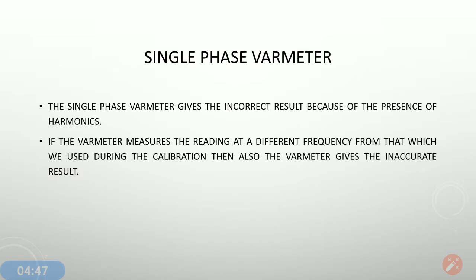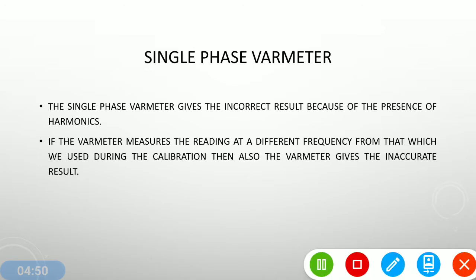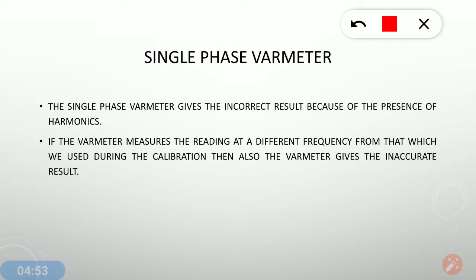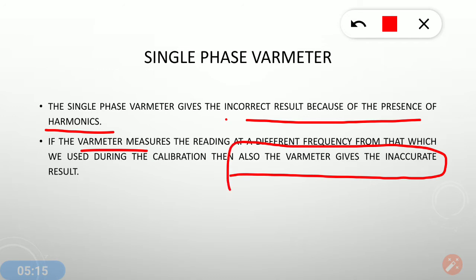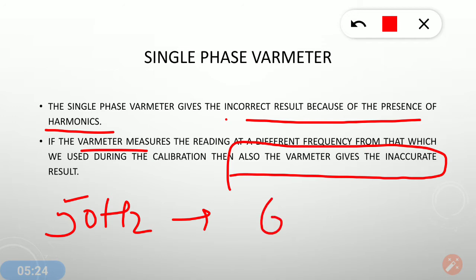There is a disadvantage of the single phase VAR meter: it produces incorrect results because of the presence of harmonics. Also, if the VAR meter is used at a different frequency from the one used during its calibration, it will give inaccurate results. For example, if the meter is calibrated for 50 Hz and you are measuring power at 60 Hz, it will definitely give erroneous results.